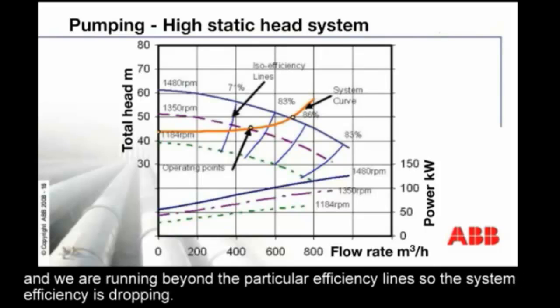When we go to a system where there's a higher static head, in that case the amount of speed turndown is not so great. We're running beyond the particular efficiency lines, so the system efficiency is dropping.